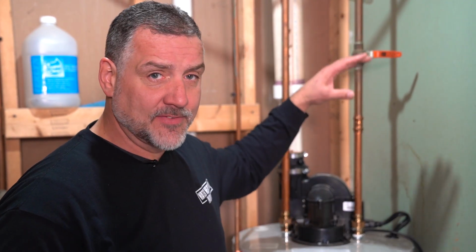Okay, this is a video on how to change out an anode rod on a Bradford White heater. Whether it's an electric heater or an atmospheric vent that has a metal vent that comes off the top, or a power vent like in this case, it's the same process on all three. So if you have a standard residential Bradford White heater, I'm going to teach you how to change the anode rod out on the unit.